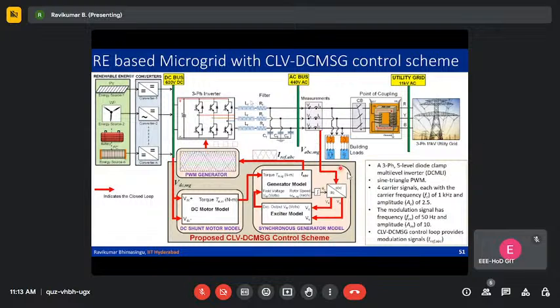From the implementation point of view, we have renewable energy sources connecting to a DC bus, 600 volts DC bus, using their local controllers, and a 440 volts AC bus, which is connected to the utility grid at 11 kV using step up transformers. This we have considered as the point of coupling, and here we have some building loads.